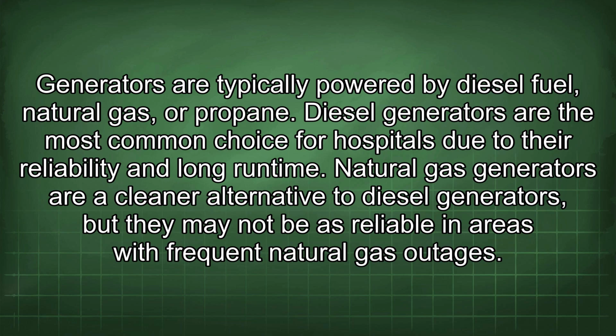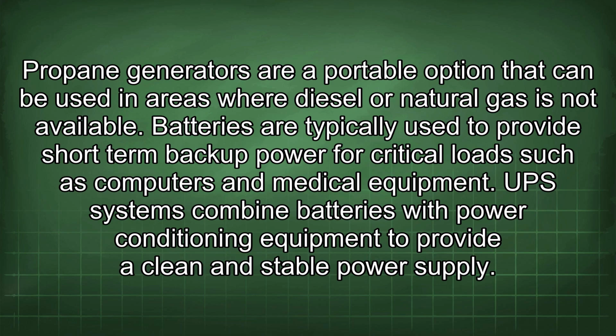Natural gas generators are a cleaner alternative to diesel generators, but they may not be as reliable in areas with frequent natural gas outages. Propane generators are a portable option that can be used in areas where diesel or natural gas is not available. Batteries are typically used to provide short-term backup power for critical loads such as computers and medical equipment. UPS systems combine batteries with power conditioning equipment to provide a clean and stable power supply.